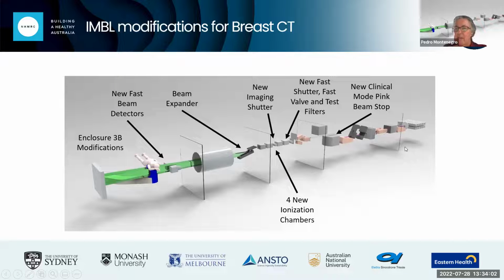So once we have produced a monochromatic beam using a monochromator here, this is a 2 crystal monochromator. Typically at this stage, we produce 30 kilowatts of X-rays. By the time we come out of a couple of components, a mask and some filters in the front end, we've taken this to about 3 kilowatts.